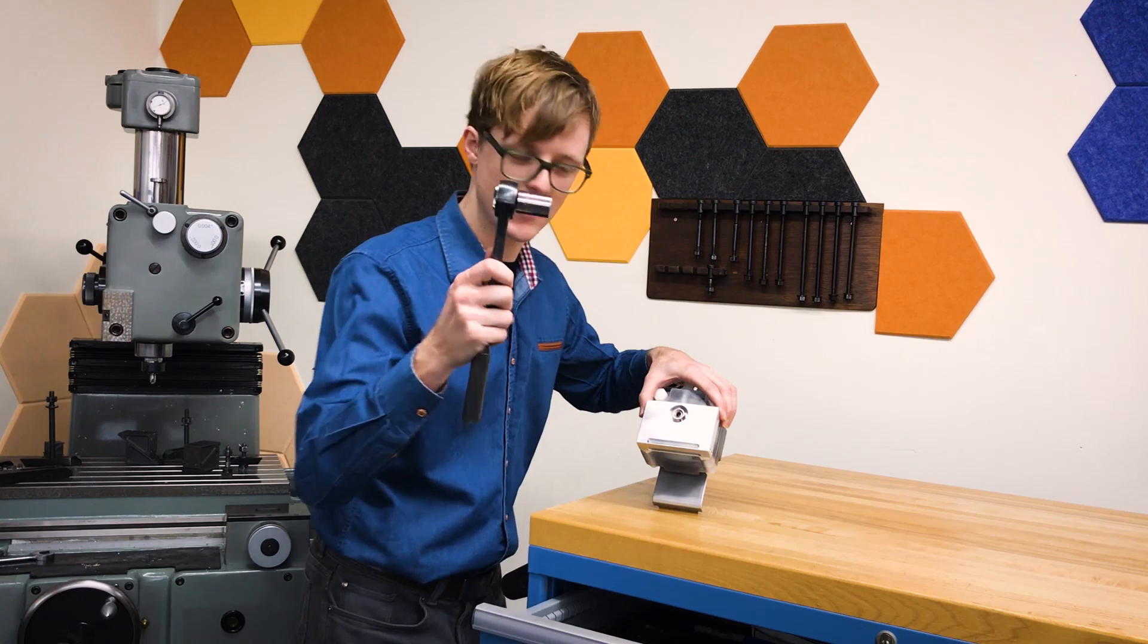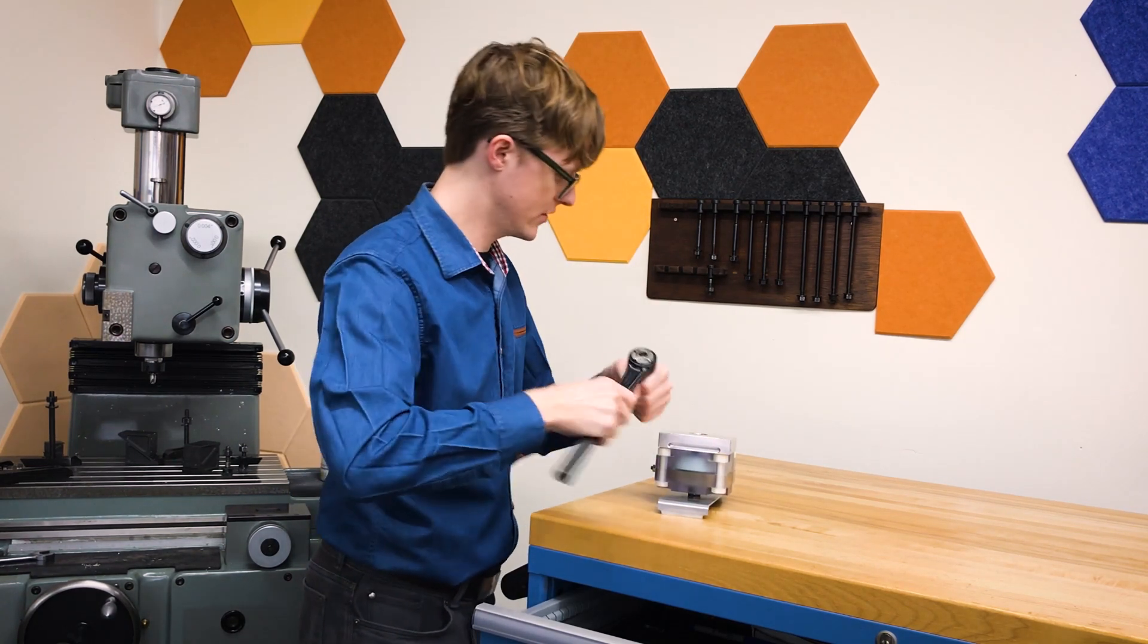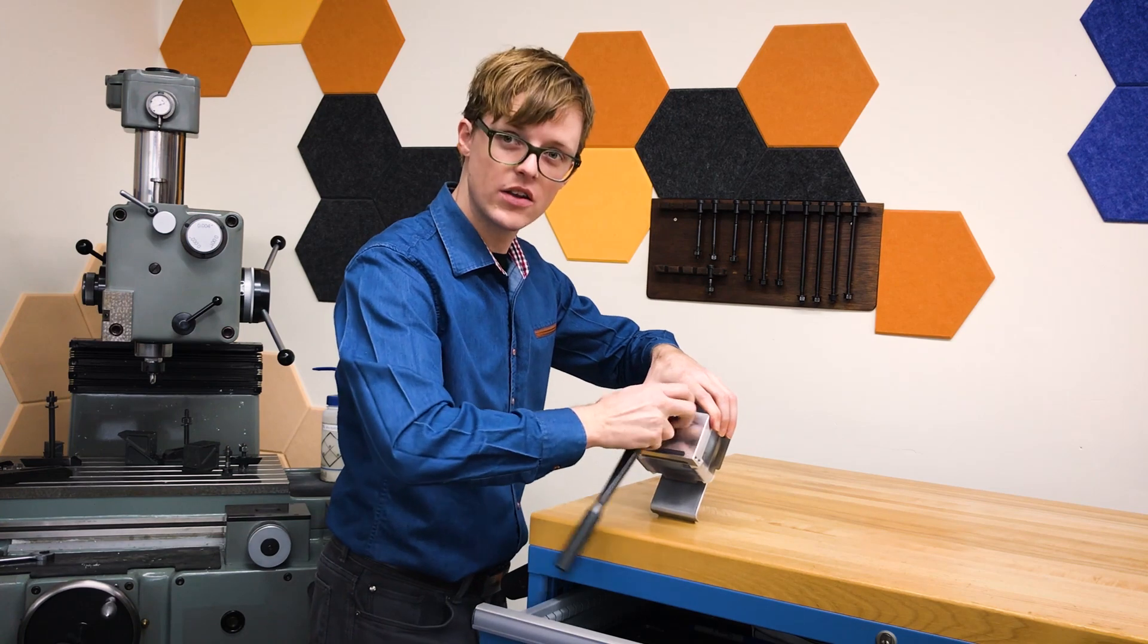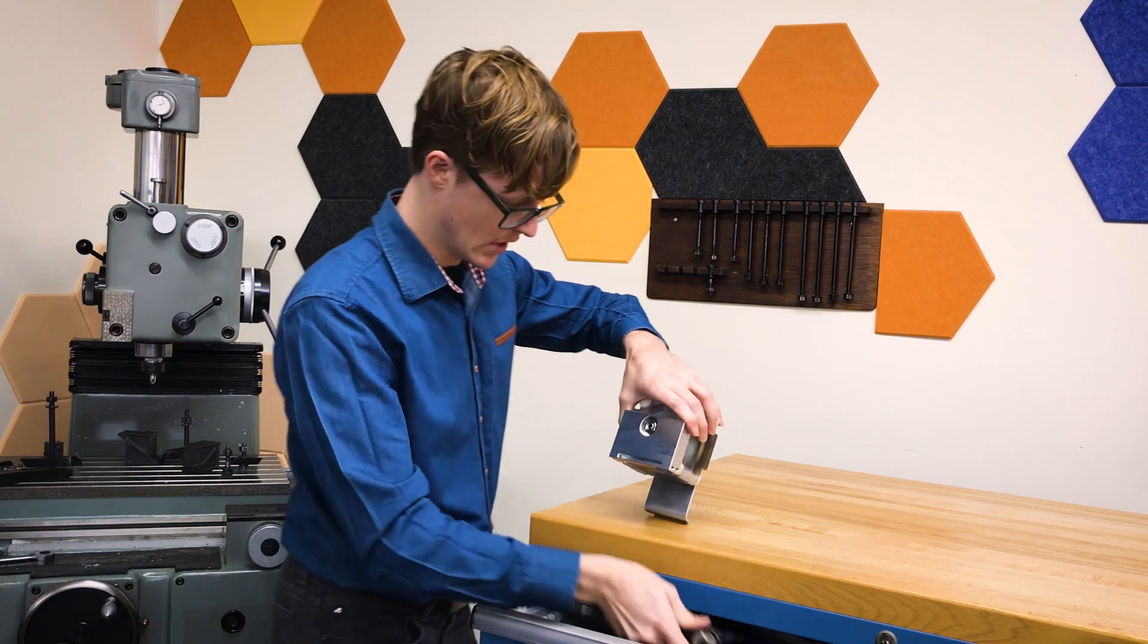Then I'm going to grab a socket wrench, make sure this is going the right direction, and snug up that nut onto the connector. Okay guys, we've got the main things done here. The two bus bar connectors are hooked up - can easily have 50 kilo amps go through this switch now. Now we need to deal with the trigger terminal.